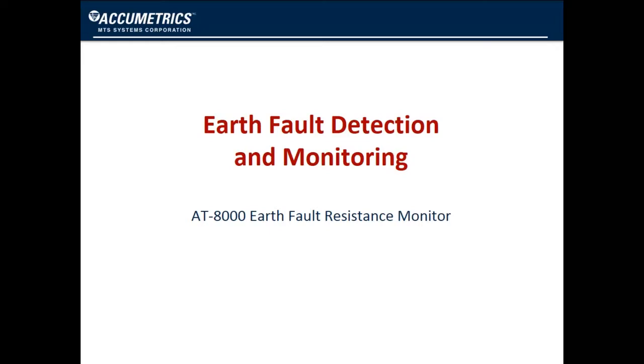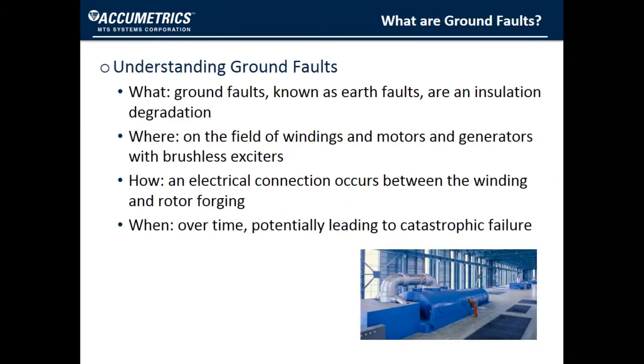Earth fault or ground fault monitors detect faults on the field windings of motors and generators with brushless exciters. On generators, a field ground fault, also known as an earth fault, is defined as an insulation degradation or breakdown that can lead to an electrical connection between the field winding on the rotor and the rotor forging. This electrical connection can potentially lead to catastrophic failure over time.